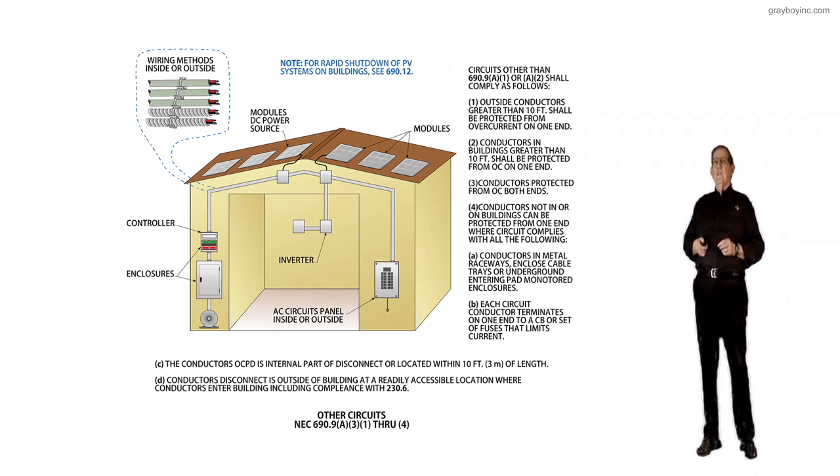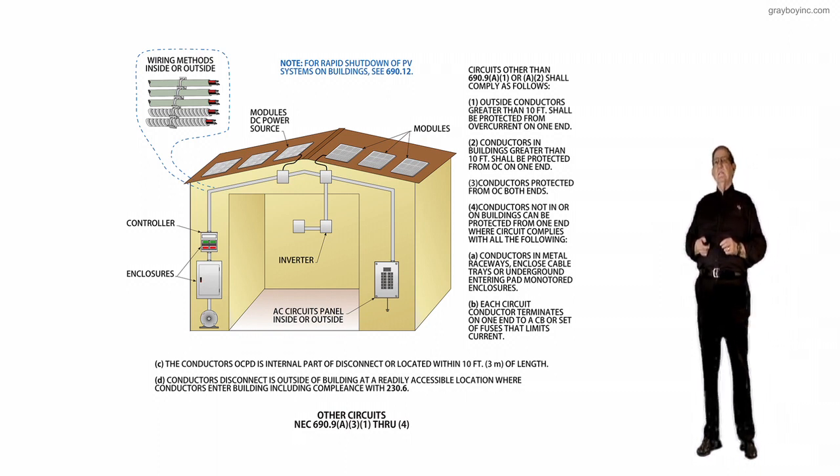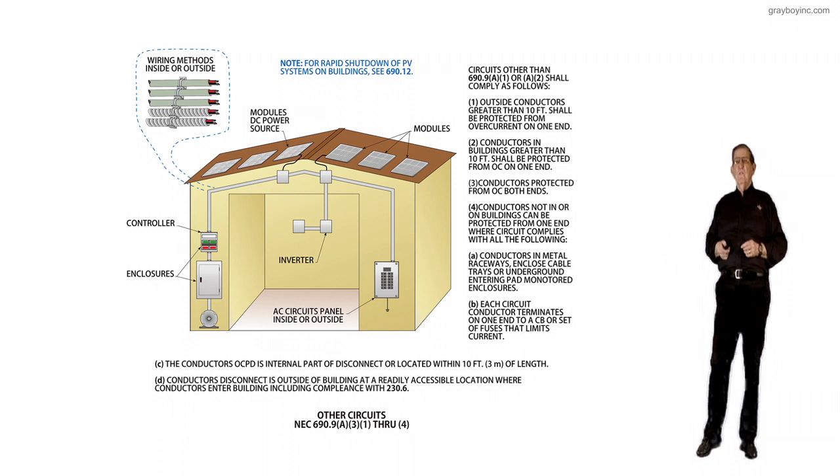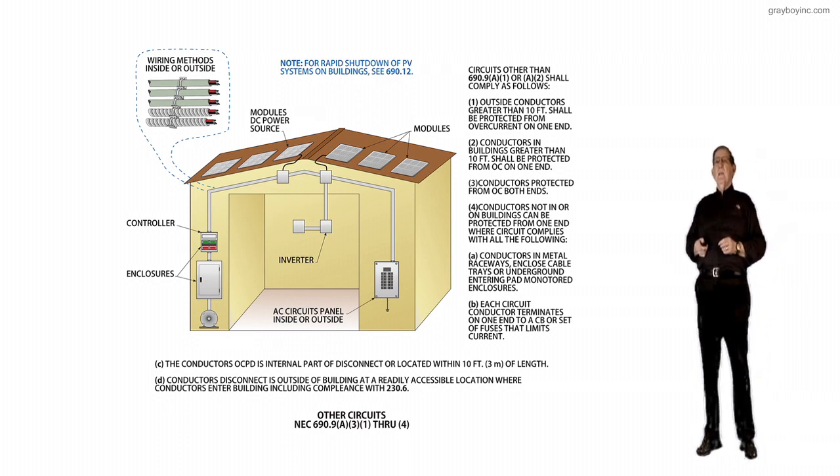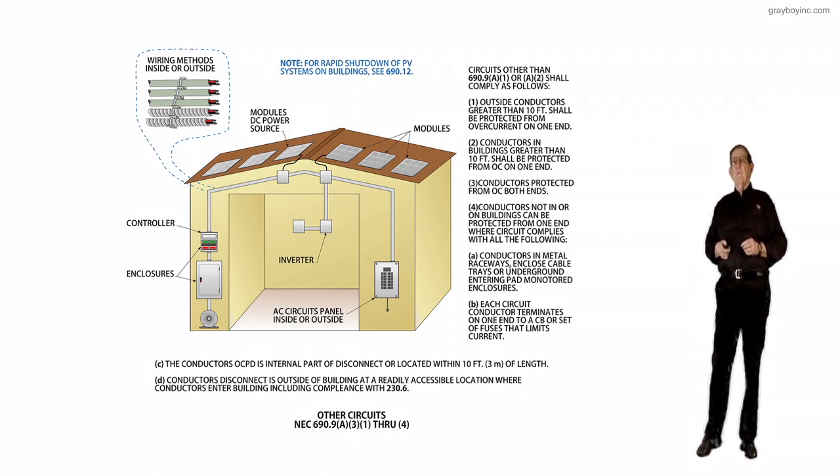Three, conductors protected from overcurrent on both ends would be required to be done so by this new subsection. Then notice four, conductors not in a building can be protected from one end where the circuit complies with all of the following.